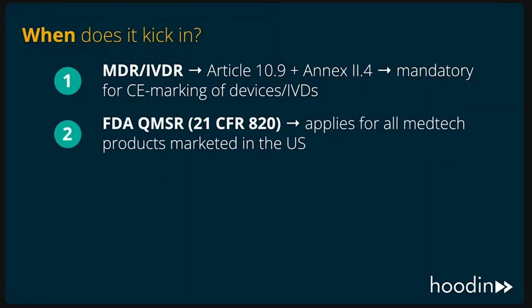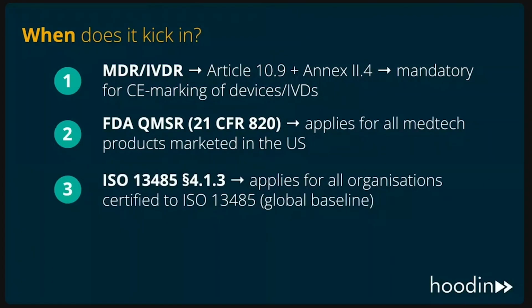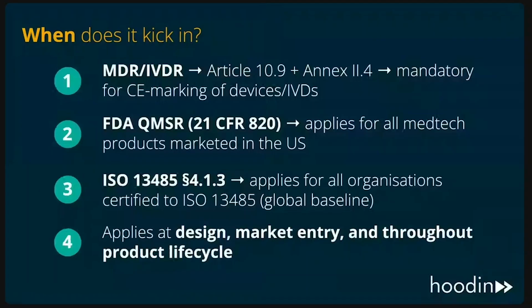And then you find a similar thing in FDA QMSR, all medtech products and IVD products, same thing. ISO 13485 applies for all certified organizations, global baseline. So it's kind of hard to get away without this for compliance reasons, and it applies throughout the entire life cycle. You need this already at the design phase, right? Because it's the backbone of your regulatory path, and it will help you a lot. If you start out with this, pretty much one of the first things you do, you will have it with you.